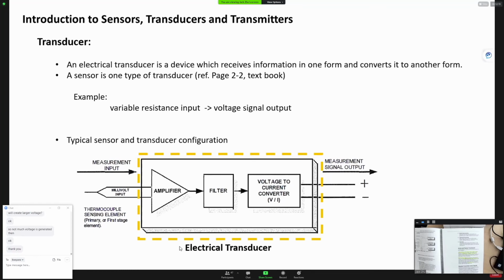You could have an electrical transducer, which is always converting to either voltage or current. Other types of transducers might convert into air pressure, or into a temperature. So you could use a thermocouple down here, measure the millivolts, increase the value, use a filter, or put a microprocessor or display down here to actually show the temperature.